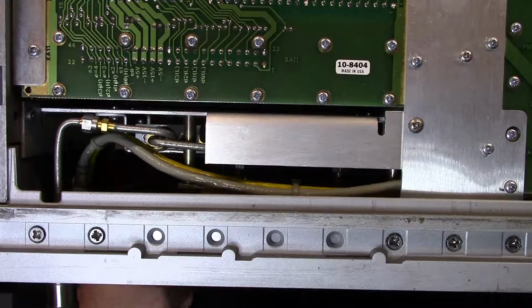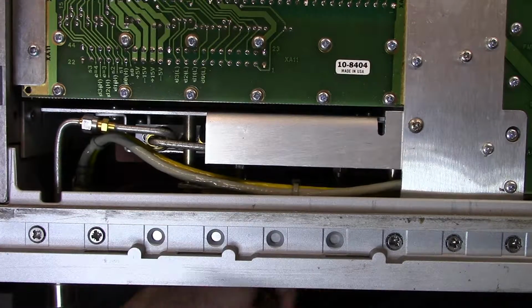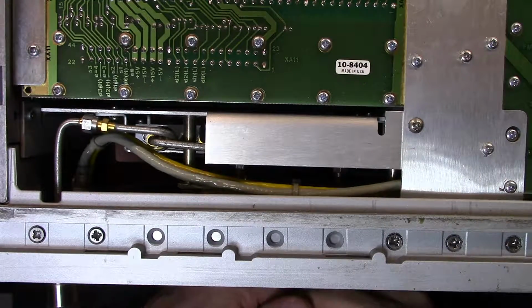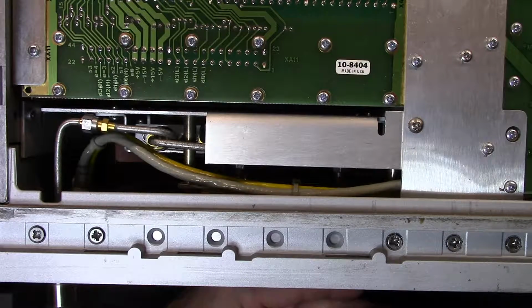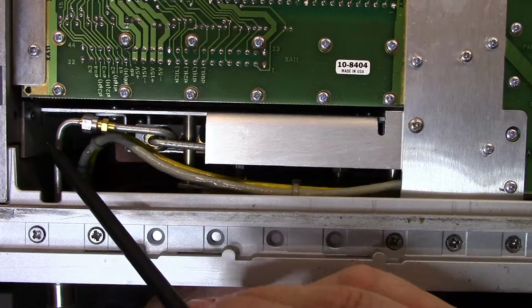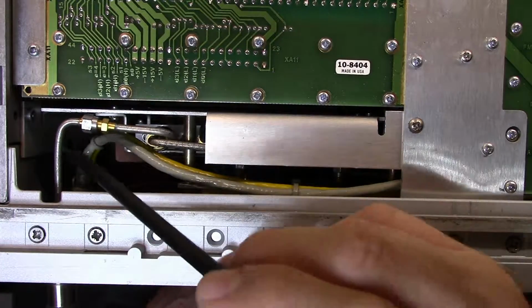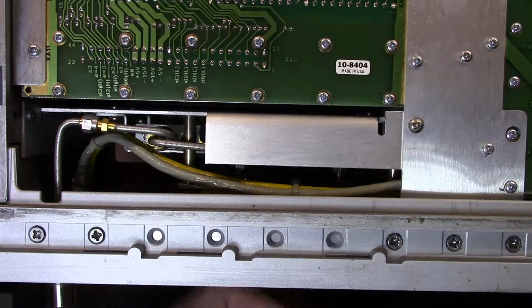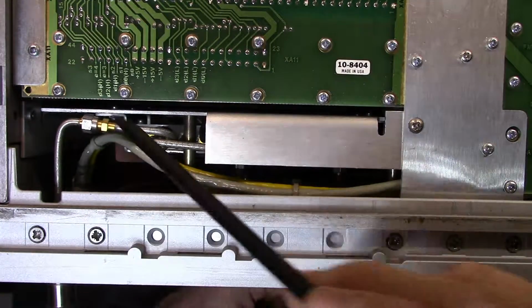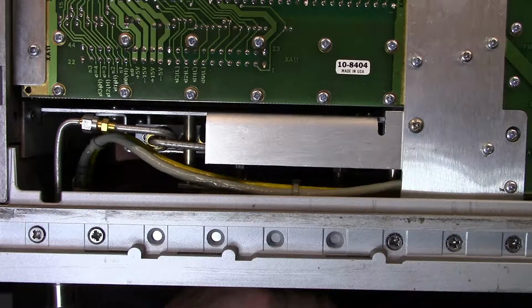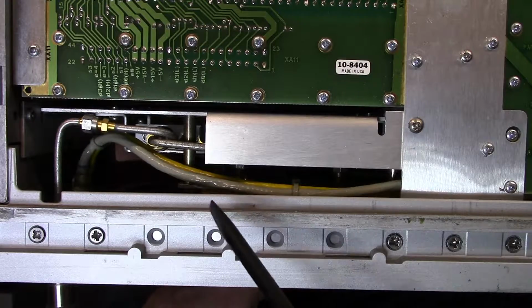What I have here is my 89028. I've run it through all of its calibration tests and it fails two tests. The first one it fails is the SWR test, which is measuring the standing wave ratio from the input over here. And the second test it fails is the tuned RF level.